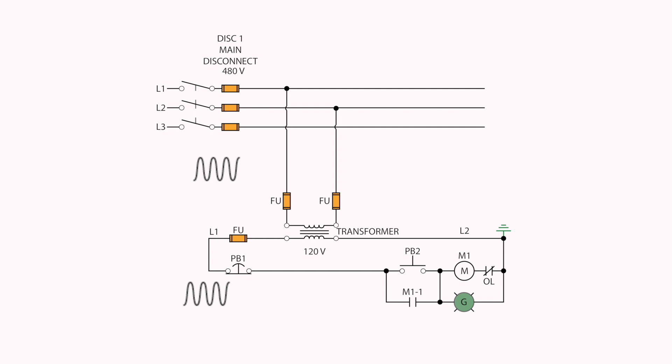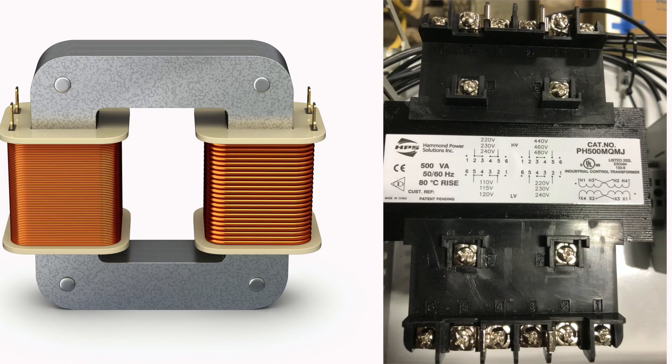Also, a transformer doesn't change power levels between circuits. If you put 10 kilovolt amp into a transformer, you will get 10 kilovolt amp out. There are losses, but the losses are very minimal and can almost be ignored. The average efficiency of a transformer is well over 90%, and that can be attributed to the fact that a transformer has no moving parts.